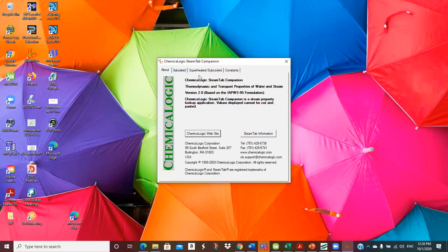And what was our gas price in here? $3.50? I think it was $3.50 a million, times 3.5. Well, that's $9.76 an hour times, if it's a whole year, 8760. Well, that's 85,500. So that's another option.